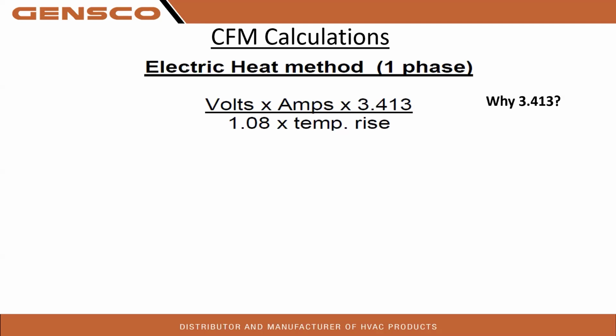And then where do we get the 3.413? Because that is how many BTUs per watt. So when they were sizing ACs for agricultural, they would take those bulbs that were providing the UV for the plants and how many BTUs were needed per watt of the light. That's how they're going to size the AC. So that's a good real world application.